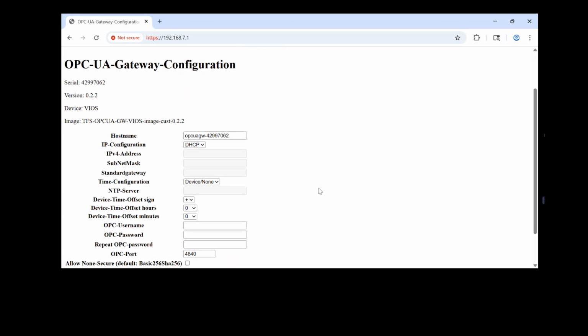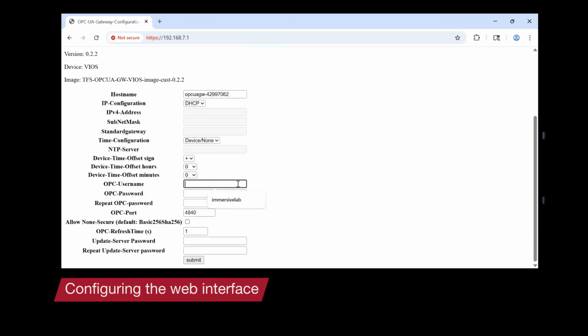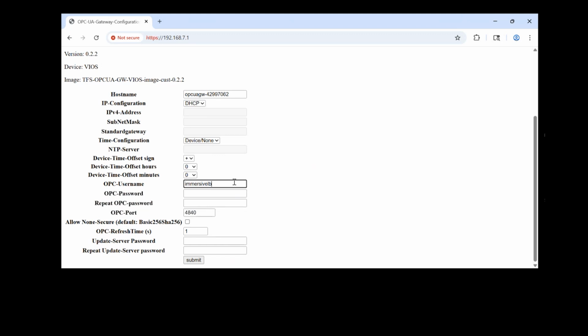Wait until the connection to the IP address has been made and the web interface will appear. From the web interface screen, you can set up the OPC UA server IP address for both subnet mask and standard gateway, the OPC username and password, and the password for the update interface. You will need to define the OPC username and password for this initial configuration. You should also make note of these credentials for future reference.